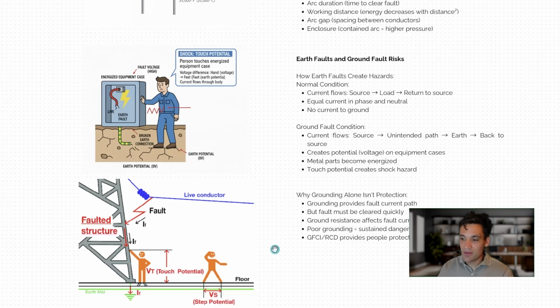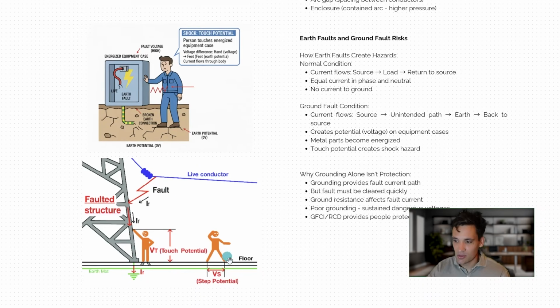The other way you could have a properly grounded system and still have people get some sort of electric shock under a fault condition is referred to as step potential. So what happens with step potential is, if you can imagine this faulted structure, the return path of this live conductor is back at a transformer kilometers away. That return path, when there's a fault, should flow through the structure, flow through the earth, back to the earth at the transformer, completing the circuit from the fault.